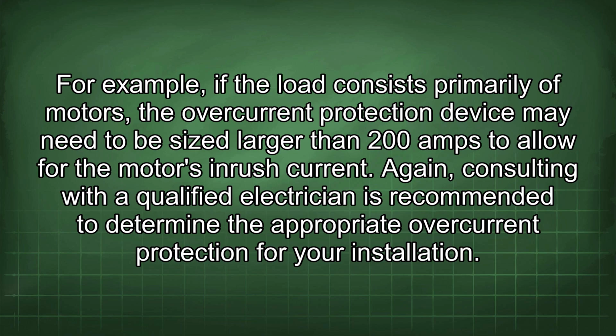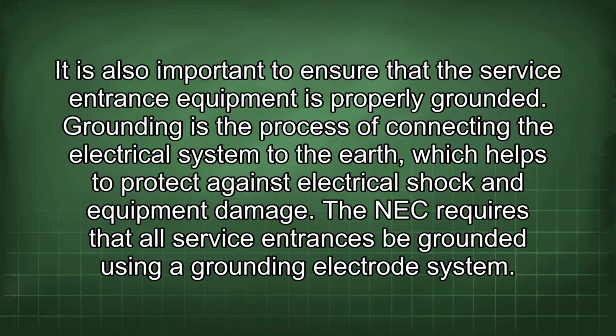Again, consulting with a qualified electrician is recommended to determine the appropriate overcurrent protection for your installation. It is also important to ensure that the service entrance equipment is properly grounded. Grounding is the process of connecting the electrical system to the earth, which helps to protect against electrical shock and equipment damage. The NEC requires that all service entrances be grounded using a grounding electrode system.